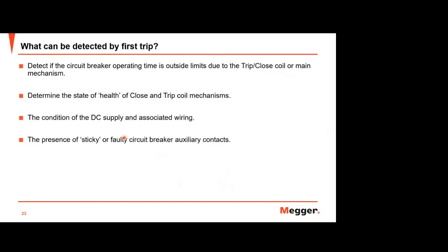What can be detected by first trip? You can detect if breaker operating time is outside limit, for trip and close. And also you can determine the state of health of the close and trip coil mechanism. Is there any effect with the lubrication, or maybe dry use, or any mechanism issue you can detect?